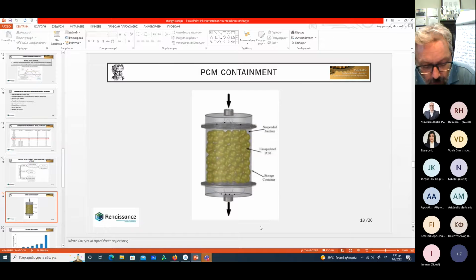During the charging mode, hot fluid from the solar field, for example, is circulated through the tank. The PCM inside the capsules absorbs latent heat and melts. During the discharging mode, cooler heat transfer fluid is circulated through the tank to absorb heat from the PCM, causing it to freeze. The heated fluid is then used to heat the power block's working fluid through a heat exchanger.